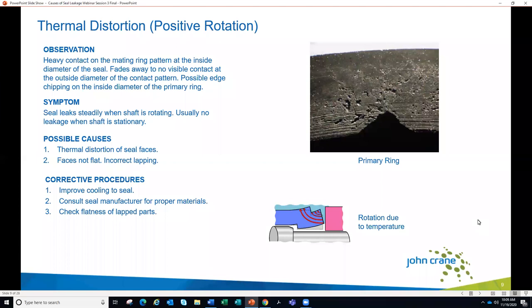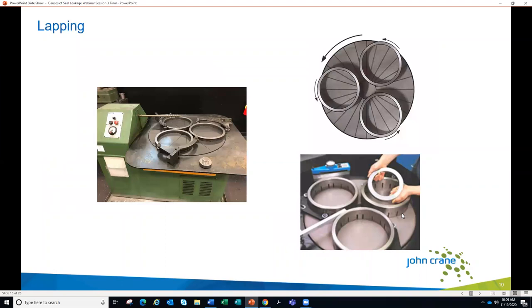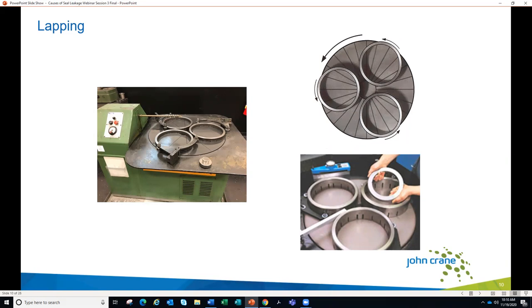We need to make sure we are lapping the faces flat. The process is referred to as lapping, using a lapping table as seen on the left picture. On top of the lapping machine we have the lapping table surface — the main larger circle in the middle — a set of three conditioning rings, and our seal faces placed within those conditioning rings. As the lapping table and conditioning rings rotate, it keeps the seal faces moving so the lapping procedure is carried out at an even rate. We provide weight or pressure to the back of the rings to get the required amount of lapping. Oil or water-based mixtures with an abrasive material are typically used when lapping carbon primary rings.